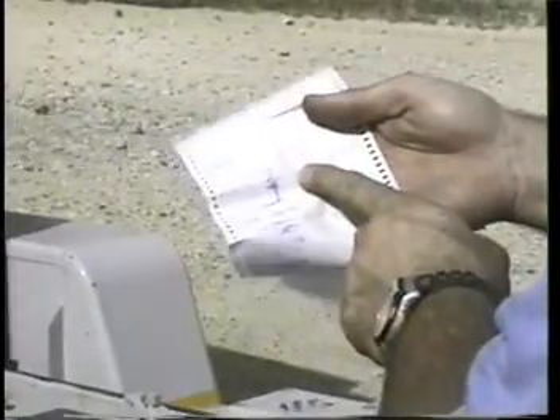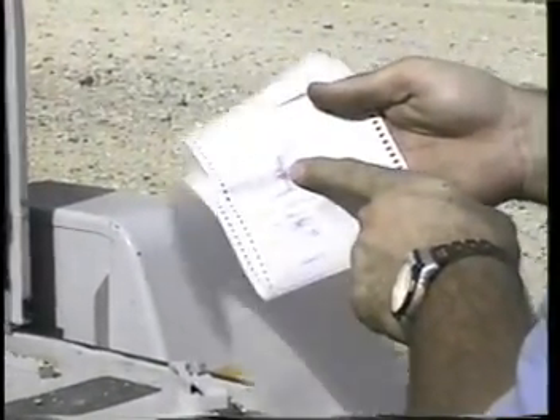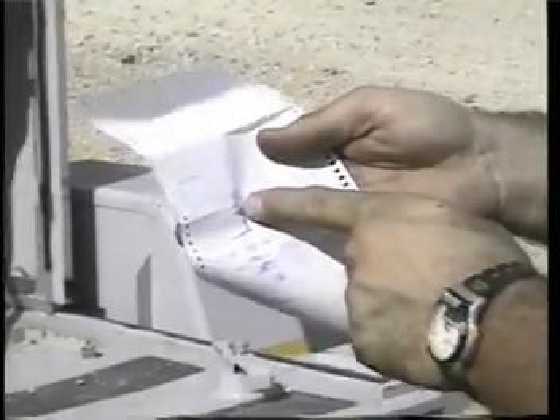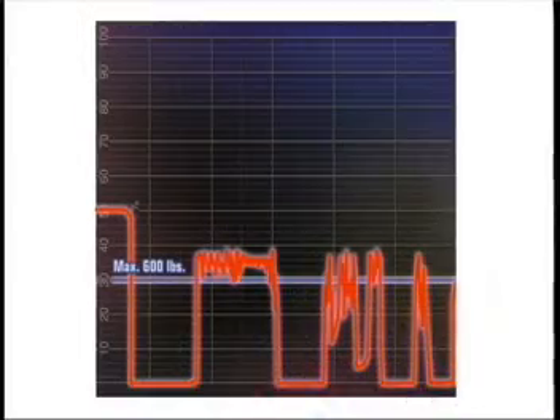A Condux electronic control system was used to measure tensions and precisely monitor the force exerted on the cable during both the Muletape and the polyrope pulls. Each foot of the pulls was recorded and documented by the Condux chart recorder. Anything over 600 pounds is over the fiber optic manufacturer's guidelines for tension.